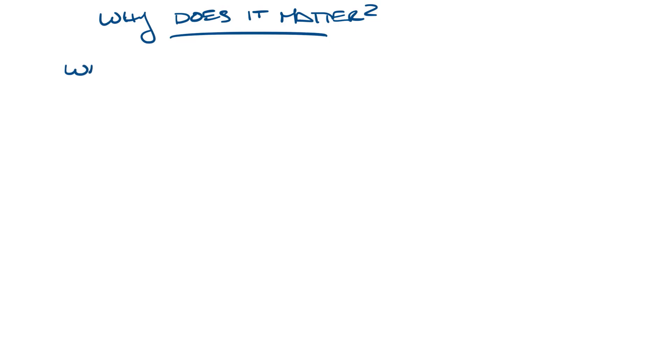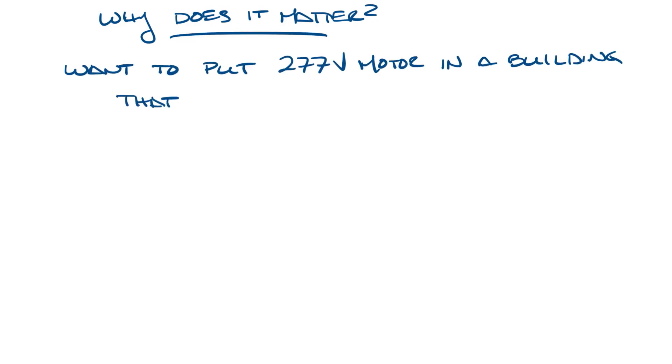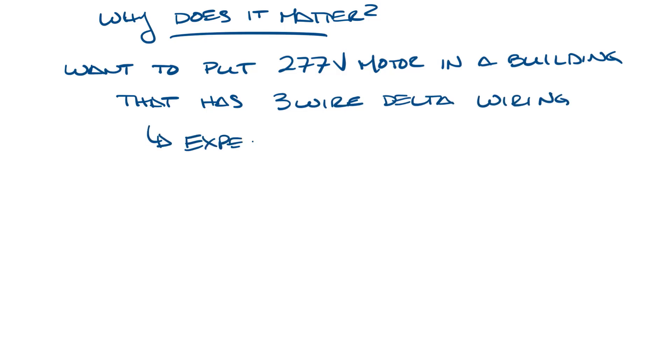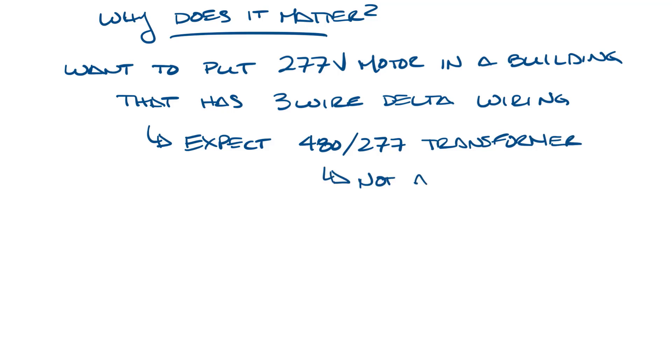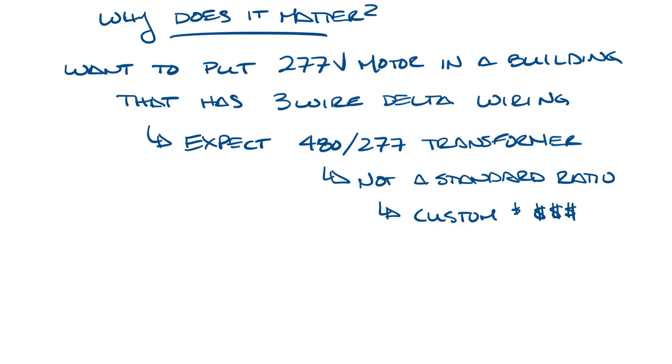This frequently comes up with 277 volt motors on fan boxes in buildings that have the Delta configuration. Sometimes people expect a 480 to 277 volt transformer if they get a 277 volt fan box, but 480 to 277 volt transformers are not a standard transformer ratio, so they would be custom wound, and that would make them more expensive.